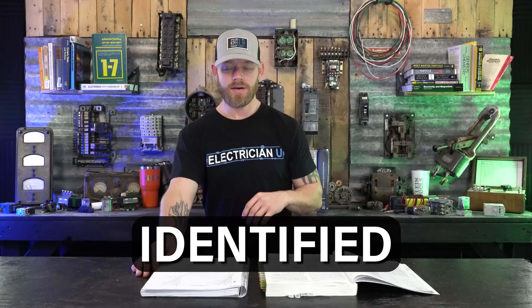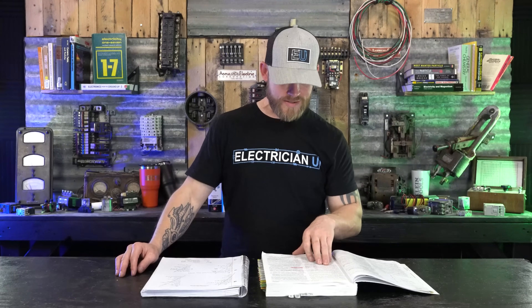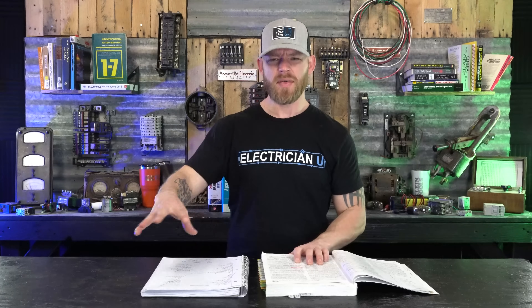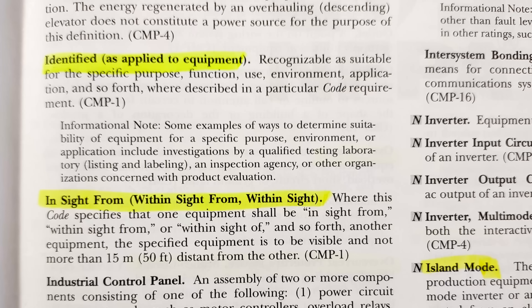The last term is identified. Identified means you're putting something on something to call it a name — essentially IDing it, recognizing it as suitable for the specific purpose, function, use, environment, and application where described in a particular code requirement. So a piece of equipment might need to be identified for its voltage, KVA rating, or horsepower. The people doing the identifying would be an authority having jurisdiction, UL, some kind of inspection agency, or testing laboratory — but it doesn't mean the same thing as listing or labeling. Those three terms get thrown around a lot and get confused.